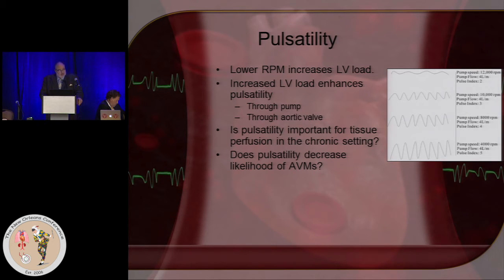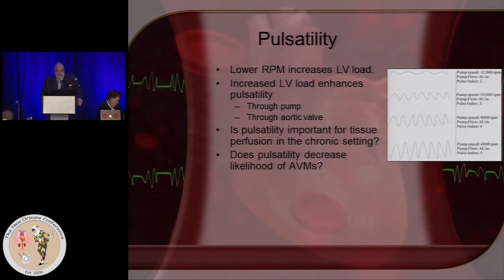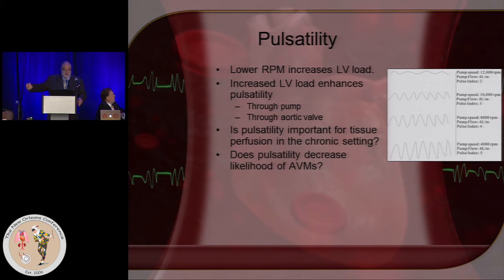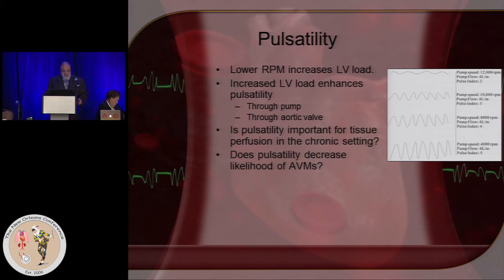Pulsatility: if you lower the RPM, we fill the ventricle more, and the increased LV load usually enhances pulsatility — both through the pump itself as the relative pressure of the LV and aorta changes, and also through the aortic valve with more blood flow through it. This relationship of increased pulsatility depends heavily on your LV systolic characteristics. There's a difference between poor LV function and very, very poor LV function. Some patients have such low LV contractility that the ventricle barely does anything — there's barely any pulsatility and it can't open the aortic valve no matter what you do.